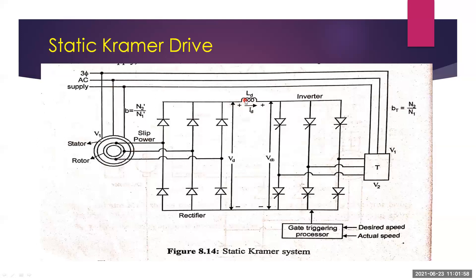The power flow is from the rotor circuit to the supply line. This method is also called a constant torque drive because the supply voltage V1 is constant and torque is proportional to V squared — so if supply voltage is constant, torque is constant. The static Kramer drive has been very popular in large power pump and fan-type drives where the range of speed control is limited to below synchronous speed.